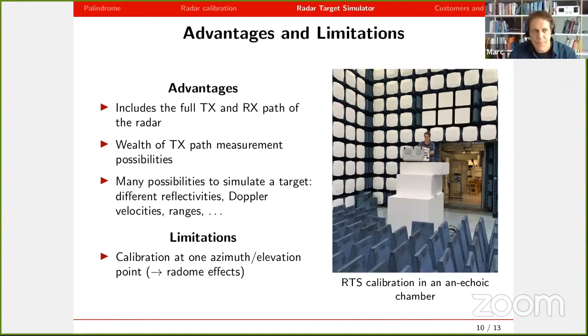So highest possible accuracy, that's the main goal. And how is this achieved? This is achieved by collaborating with the Swiss Federal Office of Metrology, which is kind of the National Institute of Standards. This office makes sure that the target we generate is traceable to SI units, and that it has really the accuracy that we claim it has. So there is a lot of testing done in the laboratories of METAS just to make sure that our instrument is really capable of providing this.